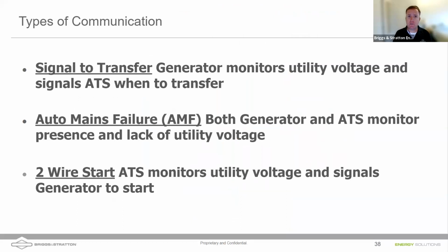There are different types of transfer switches that we offer here, and excuse me for simplifying this a little bit, but we have what are known as our standard switches and our Symphony 2 switches. The standard switch essentially works like this. The generator is monitoring the utility voltage. If it sees utility voltage drop, it's going to start itself up and then send a signal to the automatic transfer switch to go ahead and transfer, right? So the generator is kind of the brains, if you will.